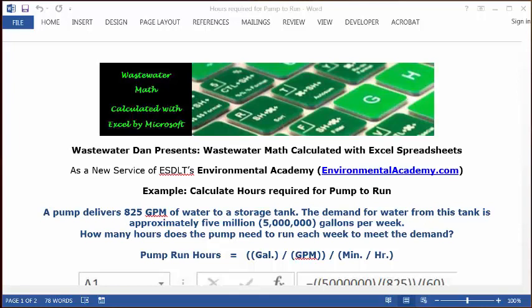We need to calculate the pump run hours. We have a flow rate in minutes and a total gallons required to pump, and we need to convert to hours. We're going to set up a basic formula: pump run hours equals the gallons divided by the gpm, divided by the minutes per hour.